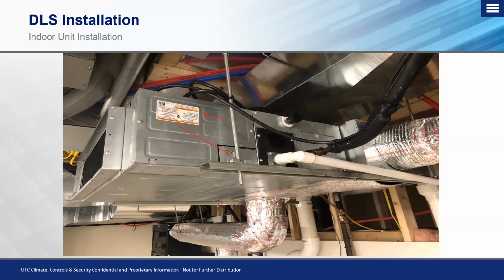But again, the surefire way to really make sure that that is not the case you're going to run into is looking at where the support hangers are. Okay, again, in this case, if they're on the bottom, the unit's upside down. They need to be at the top.